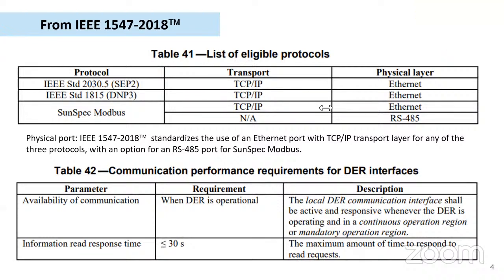And especially for larger sites, there would be no reason to have 2030.5, SunSpec Modbus, and all these ports, because there's most likely going to be a plant level controller controlling all the inverters. So that plant level controller would then communicate locally - most of them probably use Modbus right now, that's what we'll use, is SunSpec Modbus. And then the plant controller, depending on what the utility defines as their communication system.